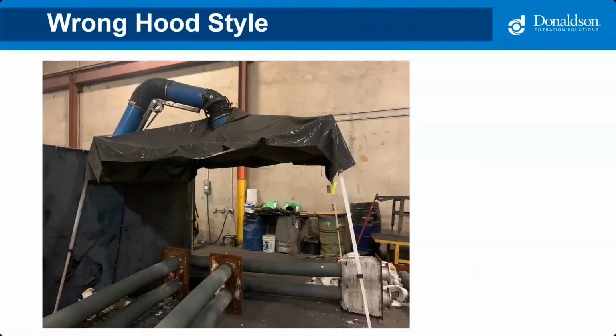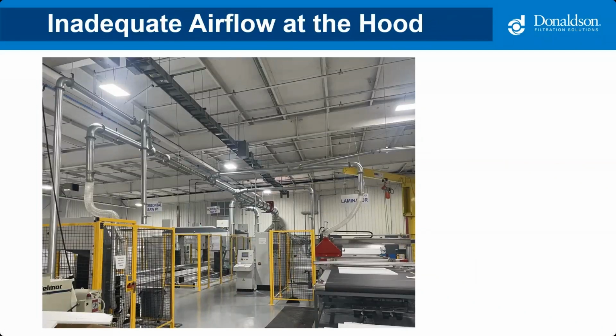And I guess one last thing on that last slide that would be important. A lot of times what I see with end users that helps a lot with this is actually two sets of slide gates. Typical, like a woodworking facility, it's pretty typical to have 4 times as many tools as employees, but they all have a ducted system. So you're opening and closing them as you're using them, and then reclosing them when you're not using them.